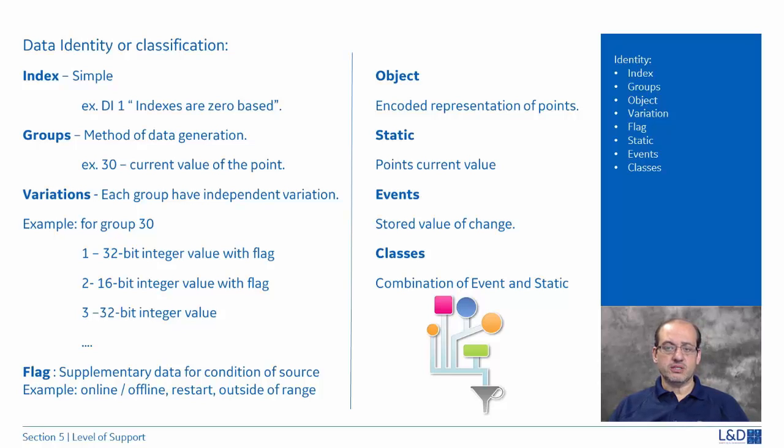And this information is referred to with an index. So the data has an index. The status of breaker 1 is referred to as DI1, right? Digital input 2 would refer to another status, maybe of the same breaker or a different breaker.